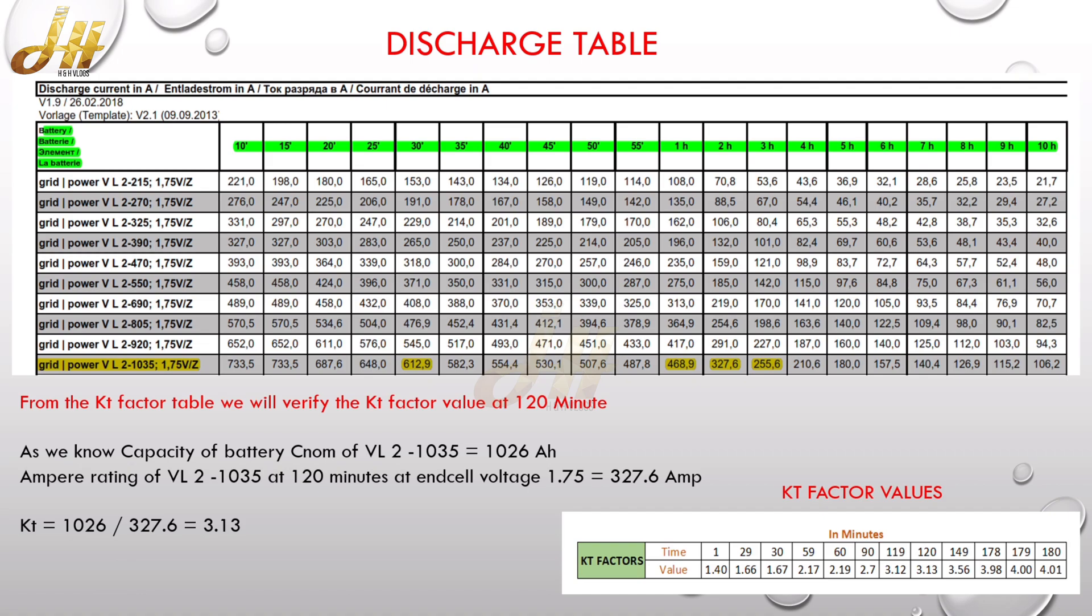So this is the discharge table of the battery at 25 degrees C. So I highlighted the battery model number, which is VL2-1035. We need to select the discharge table carefully. Since we are considering the end cell voltage is 1.75, we need to consider the discharge table also as of 1.75. So now we can see the KT factor values.